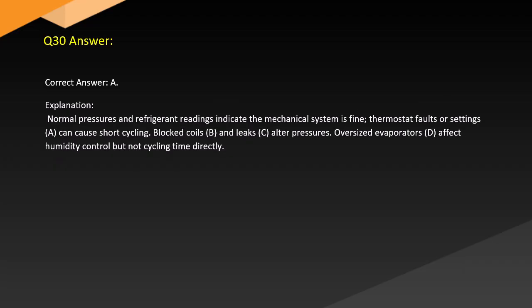Answer. Correct answer: A. Explanation. Normal pressures and refrigerant readings indicate the mechanical system is fine. A thermostat fault or settings, A, can cause short cycling. Blocked coils, B, and leaks, C, alter pressures. Oversized evaporators, D, affect humidity control but not cycling time directly.